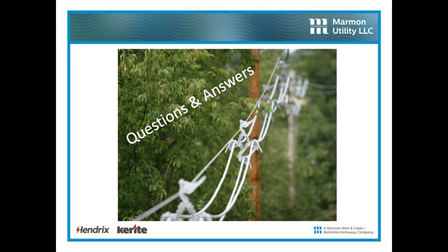Okay, great. Thanks. Can you speak about the need to keep trees trimmed so that the spacer cable does not have an insulation failure due to long-term voltage stress? Yeah, sure. Again, that's part of the maintenance program. You're going to have to do periodic tree trimming. You're going to allow intermittent contact, but you don't want permanent contact, and the more you have permanent contact, the bigger those limbs are getting.